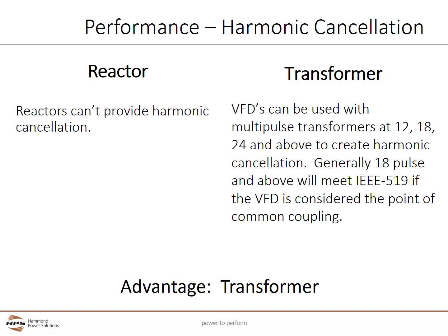This is done with phase shifting or multi-pulse transformers. These transformers typically come in 12, 18, and 24 or higher pulse configurations. All standard VFDs have 3 sets of rectifiers, one for each phase. 12-pulse means that the transformer is fed with 3-phase power, but produces two separate offset sets of three-phase outputs. The VFD then needs 6 sets of rectifiers for a 12-pulse transformer. An 18-pulse transformer has 3 separate output coils, with each set of output coils being fed to a total of 9 rectifier sections on the 18-pulse VFD.